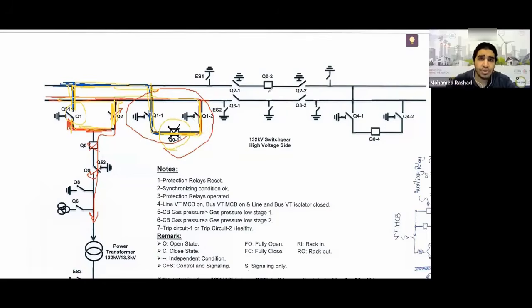No, as I told you, we will close it. I mean, we will close Q11 and Q12, so I will go to the bus coupler and close the disconnectors and then come to close the breaker. It will have the same control circuit as the breaker, and it will check that the VT isolator and the VT MCB will perform the same action that will charge it for us.